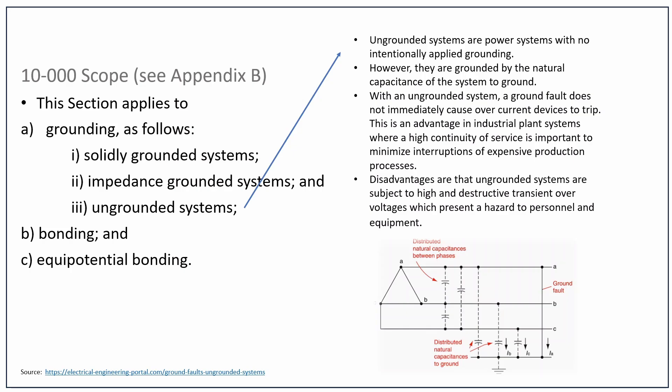Moving on to ungrounded systems — I went with the easiest example, a delta, though there are other ungrounded systems for communication systems that are a bit more complicated. An ungrounded system is similar to a delta where none of the three lines have a reference to ground — this is not the delta where one of the phases is grounded. Ungrounded systems are power systems with no intentionally applied grounding; however, they are grounded by the natural capacitance of the system to ground. Every conductor in that delta system essentially becomes a capacitor in comparison to ground. With an ungrounded system, a ground fault does not immediately cause overcurrent devices to trip, which is an advantage in industrial plant systems where high continuity of service is important to minimize interruptions of expensive production processes.